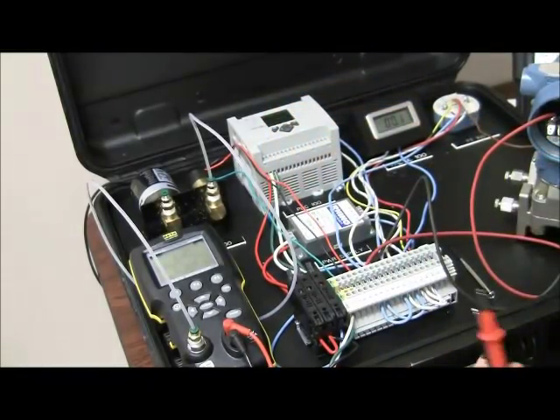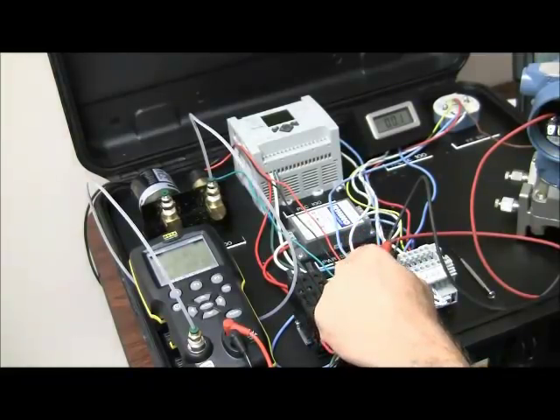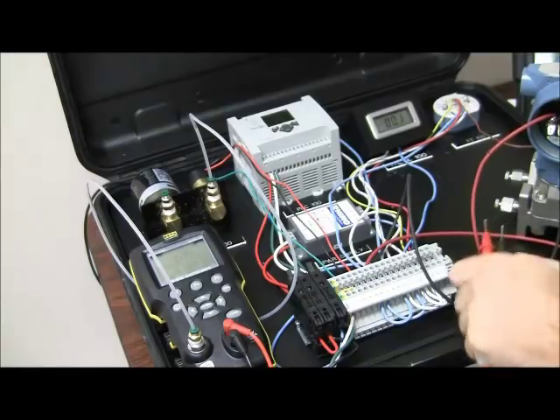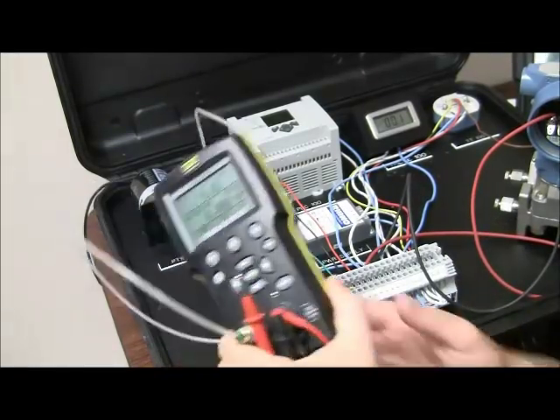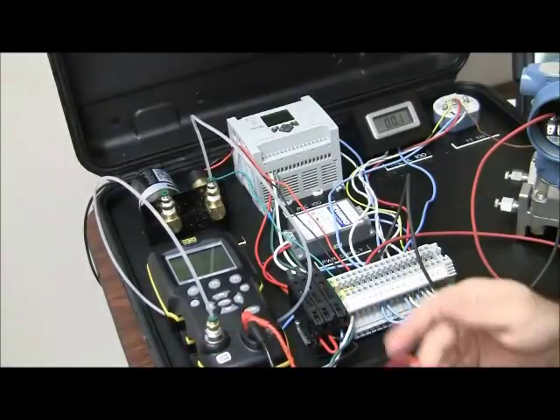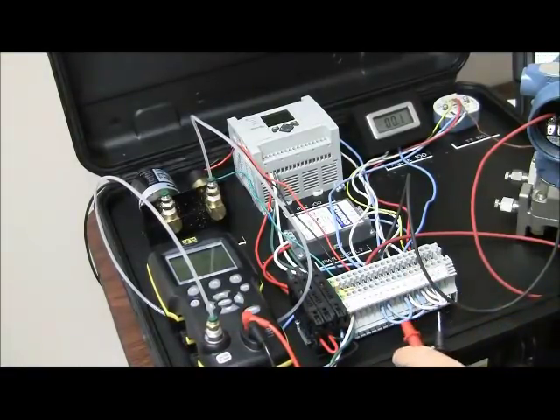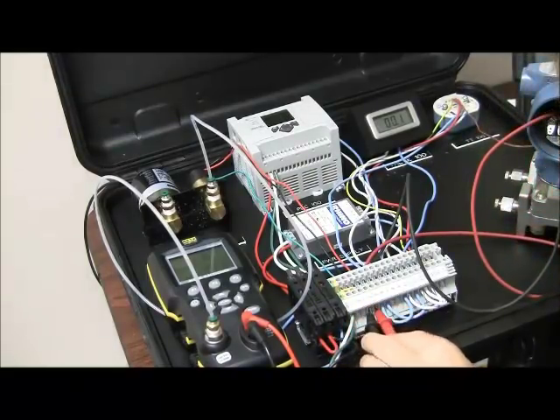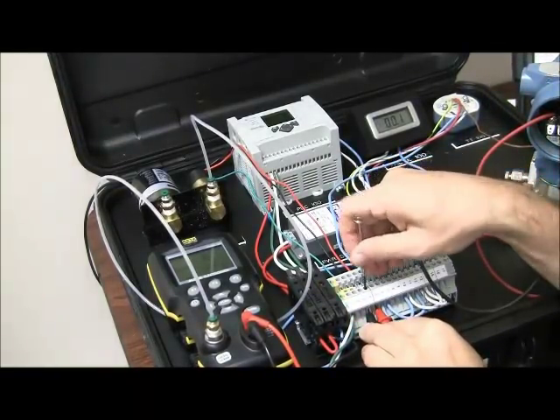So to monitor the contact closure, polarity is not important here, we're just looking for a change of state. So I'm going to run my terminals. I got them plugged into leads here in the bottom of my 330, following polarity in this case, but like I said, switch testing is not important. So I'm going to go ahead and insert my leads in the two contacts here, tighten those up.